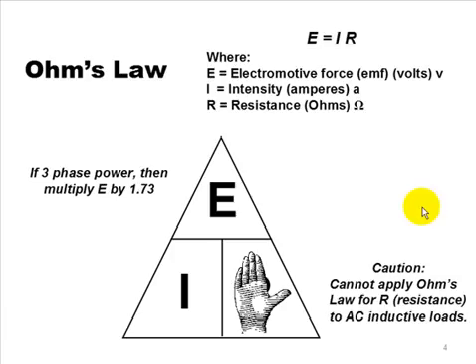Caution. Cannot apply Ohm's Law for resistance to AC inductive loads. Inductive load is a motor. Anything that draws a higher amperage when it starts as opposed to when it runs, you can't apply Ohm's Law. It doesn't work because inductance typically is associated with solenoids, coils, stator rotor windings, that kind of thing.